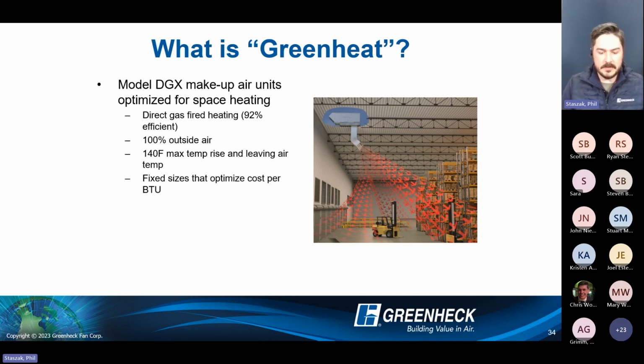The advantage of green heat is, if you play around in CAPS at all, our selection software, and search the model green heat, if you want to do a design build type application, with a large warehouse or general manufacturing facility, we've got built-in design load skin load calculations for you in the green heat selection software. All we need is perimeter. We need the roof height, how many dock doors you have, how many service doors you have. You can change the percentage of activity.